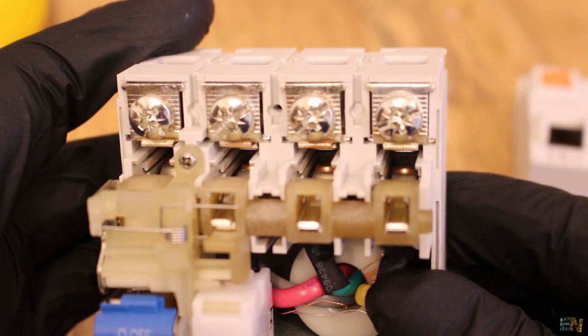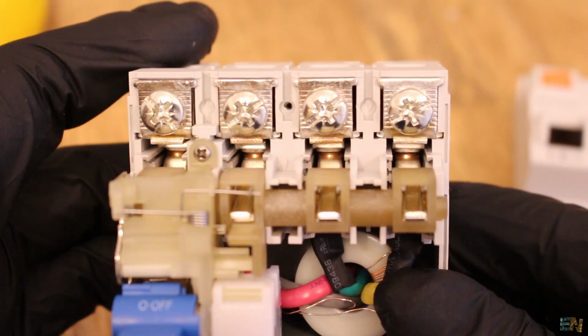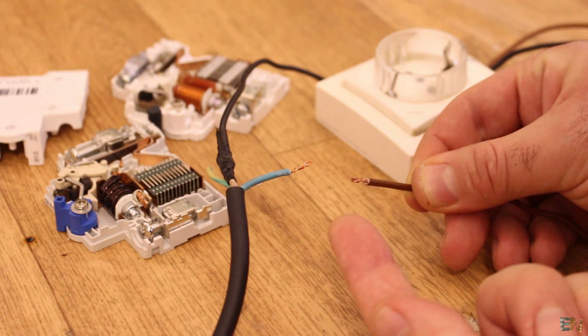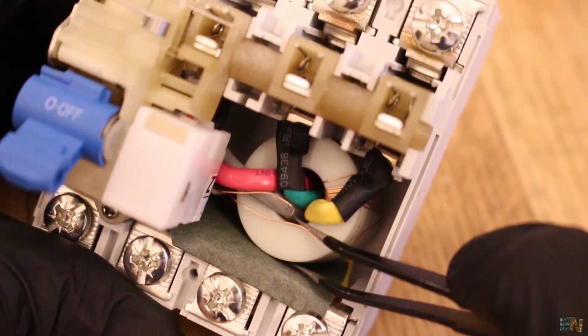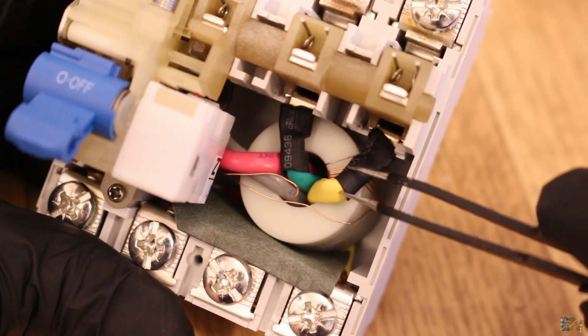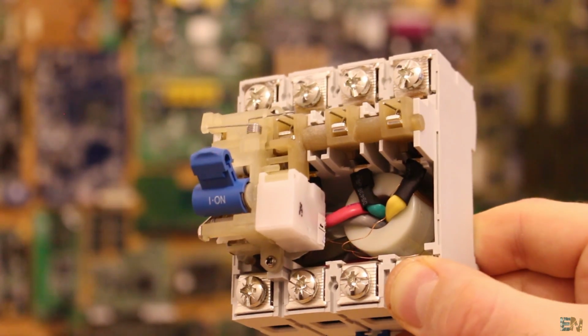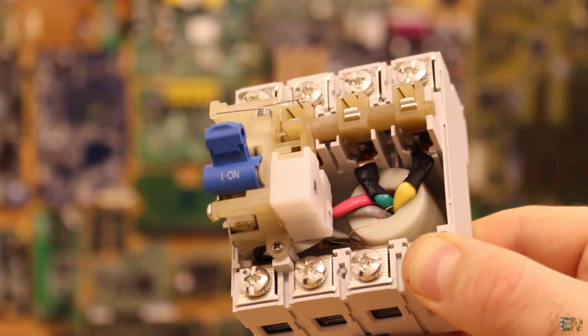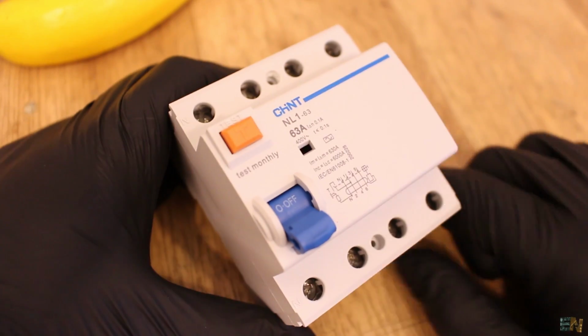It can be that I'm touching the live wire, maybe the device that I'm using has an internal short circuit between the live wire and ground, or maybe the wiring inside of my walls is getting wet, in the bathroom for example, and the small current is flowing towards ground. In all these cases, the RCCB will save our lives.